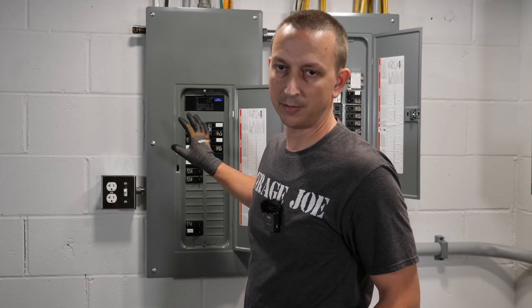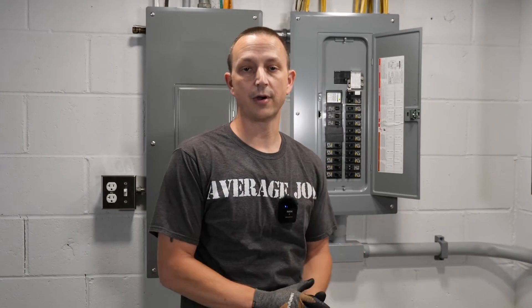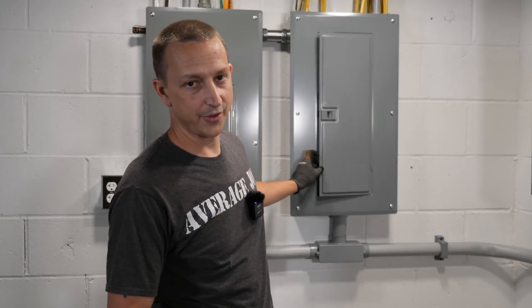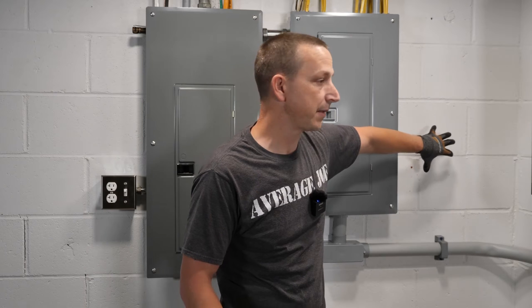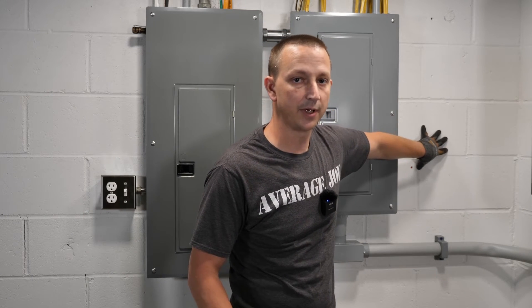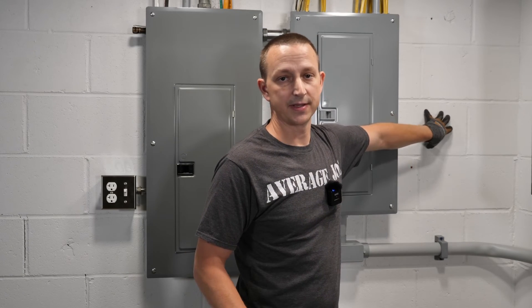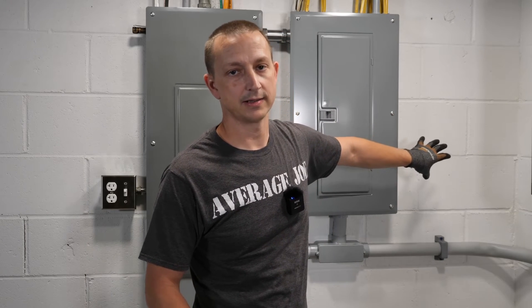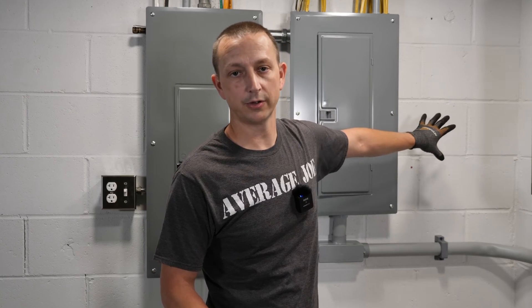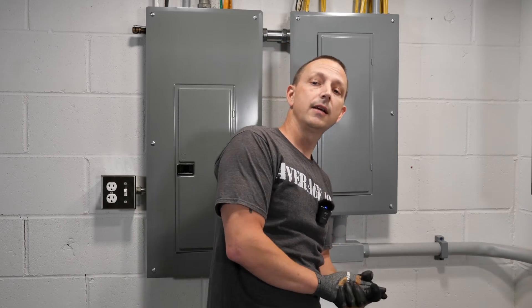For my 240-volt load, we're just going to be doing my dryer for the example today — or if you had a well pump that's 240 volts, you could do that. Now that you have those written down, the next thing is to figure out where you're going to put your critical loads panel. I'm going to be mounting mine right over here. You want to line up that flexible conduit with one of the knockouts on the side of the panel. I'm going into some cinder block, so I'll need masonry drill bits and Tapcons to mount my box. Just use the appropriate screws for whatever surface you have.